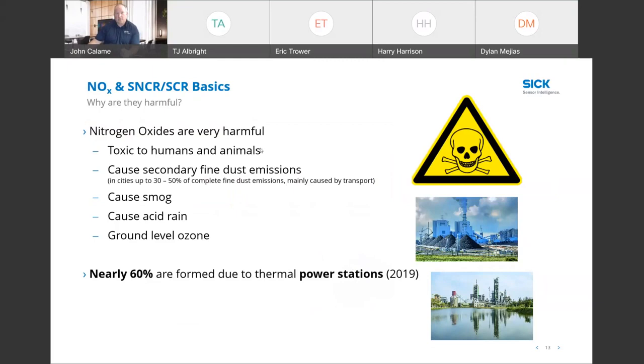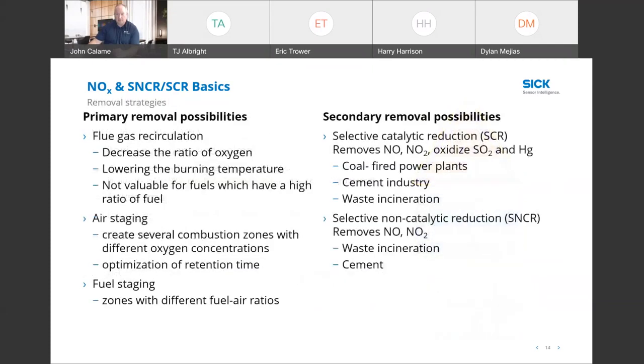So why would we measure NOx? Of course, the EPA has guidelines, and we have to do that to be in compliance. But the main reason is that there are harmful effects from nitrogen oxides. It's toxic to humans and animals. It can cause smog and acid rain and contribute to ground level ozone. A lot of the thermal power stations, power plants, create and account for quite a bit, but there are multiple sources. Automobiles and any combustion process can produce NOx.